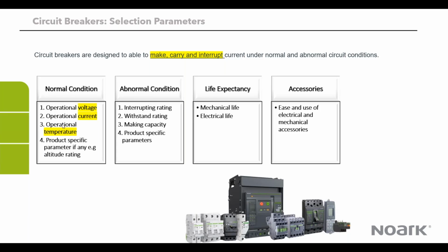The other parameter is the withstand rating, and I'll talk a little bit more about this one in later slides. Basically, it's the ability of the circuit breaker to withstand a fault within a limited amount of time. So it's not going to withstand the fault continuously, but it can stay for a few cycles before it then goes into the trip mode. The other thing is the making capacity. That's just the ability of the breaker to close the circuit. And then you have all the product specific parameters.